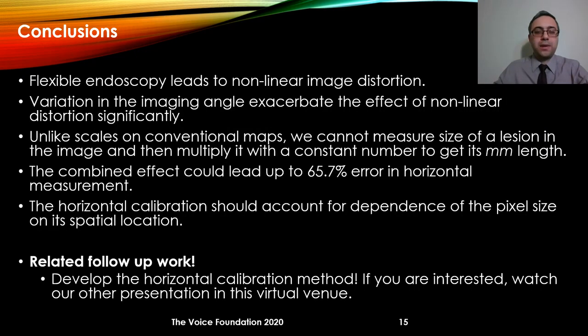In conclusion, flexible endoscopy leads to nonlinear image distortion. Variation in the imaging angle exacerbates the effect of nonlinear distortion. Unfortunately, unlike a scale on a conventional map, we cannot measure the size of a lesion in the image and then multiply it with a constant number to get its millimeter size. The analysis showed that the combined effect could lead to as high as 65% error in horizontal measurement. Finally, horizontal calibration should account for the dependence of pixel size on its spatial location. If you are interested to see how we could account for the effect of spatial location during calibration, come and see our other presentation in this virtual venue.